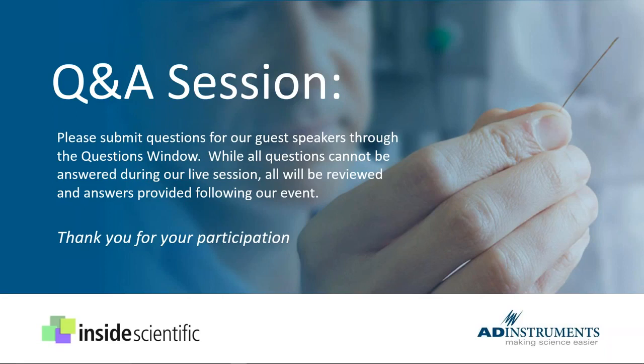Specifically, Sarah Roldan has asked, in a multi-segment catheter with 10 electrodes, in which she needs to block some of the electrodes since they don't all fit inside the ventricle, should she block the first electrodes in the catheter or the last electrodes of the catheter, or both, or what's the prescribed best practice here when you're dealing with a multi-segment catheter?